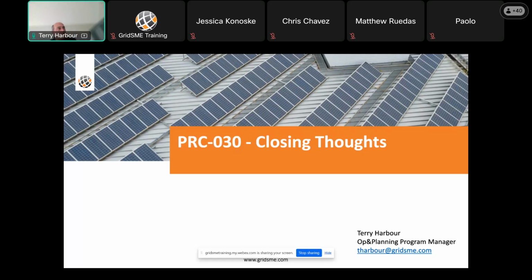I think Jay Grafton may have a question. He says he's still on mute. Yeah, I got it to work. I just want to ask, and I wanted to confirm: when we're inside the no trip zone, PRC-29, we don't have to do an analysis unless we hit these trip levels in PRC-30, correct? Is that the way the standards fit together? Yeah, I think they're somewhat tied to the hip, but if you enter that no trip zone, I know that they're going to want you to do that PRC-29 analysis.